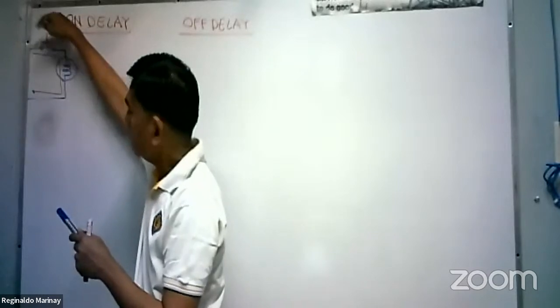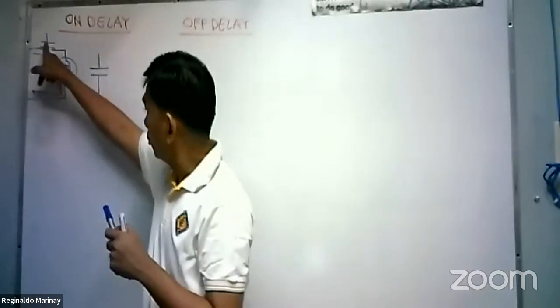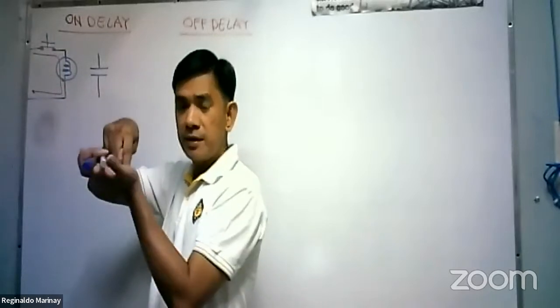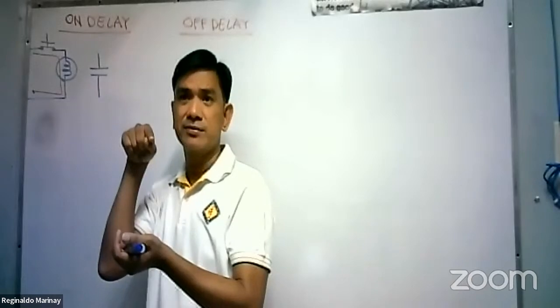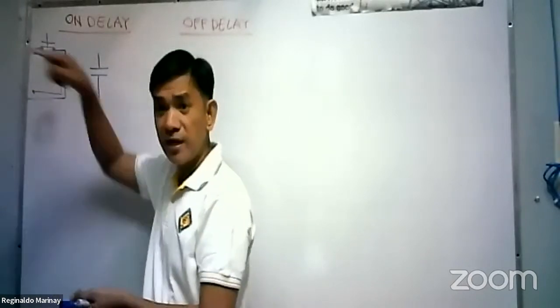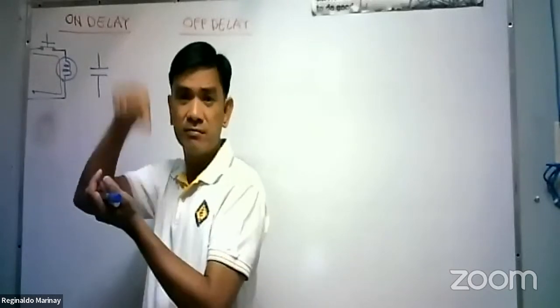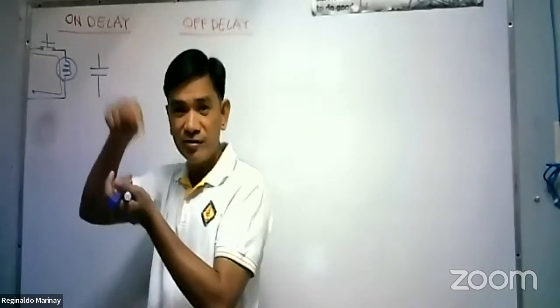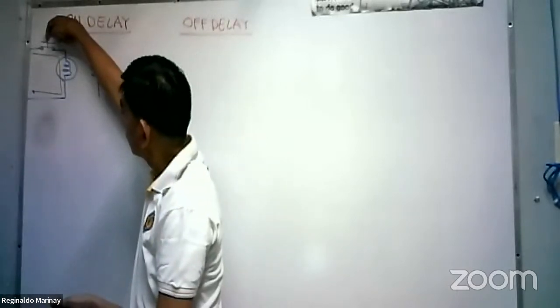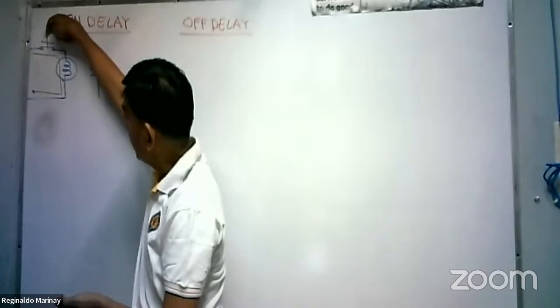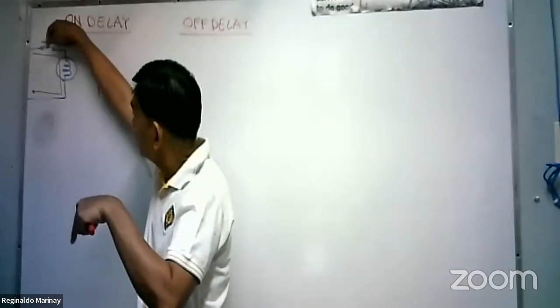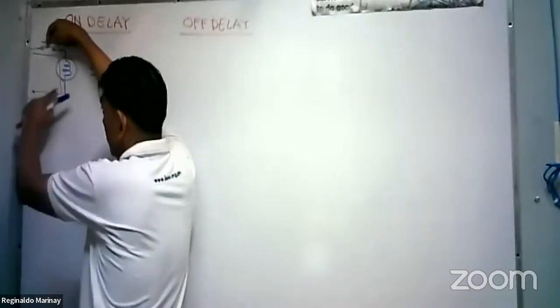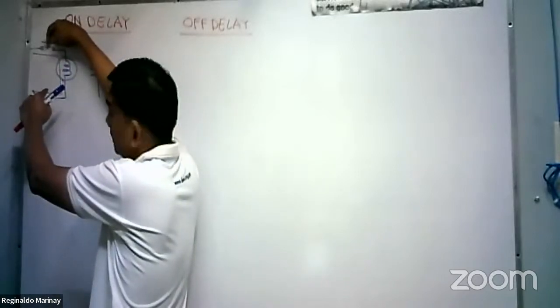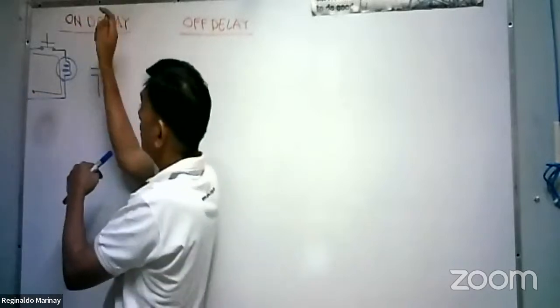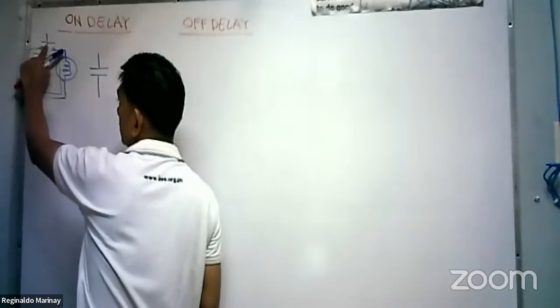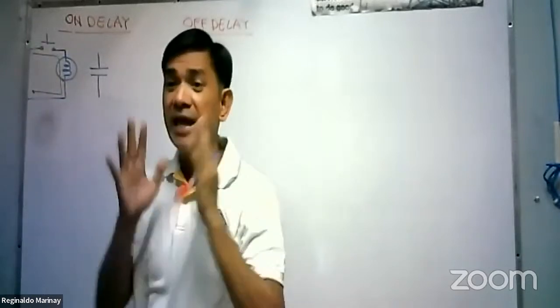There is a push button that is closed until you depress it. Meaning, this will be continuously closed as long as your finger is continuously pressing on it. Yung nakababad siya, in our language, in Filipino. So if your finger will stay there, pushing it down, this will be continuously energized. When you depress, you remove your finger, it will go back to the original position. So our holding coil will be de-energized.